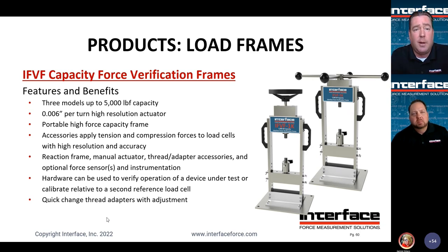In the application example earlier, I wouldn't say this is necessarily used for metrology grade applications, dependent on the transducer, of course, but more on the force verification side, whether you're trying to do a quick verify or floor level check on a load cell system. For some load cells, like Brian mentioned, some load buttons, simple load button or simple load cell type devices could do some level of calibration, particularly if you're not trying to drive to a specific load point. So if you don't need to take specific 20% intervals, perhaps this would be a good option where you're just trying to compare an output from the standard against the output from the load cell.